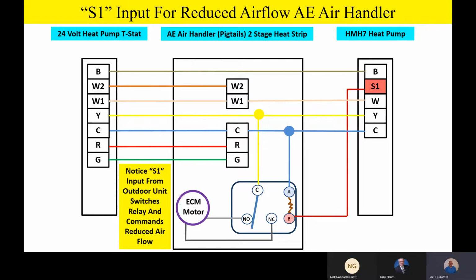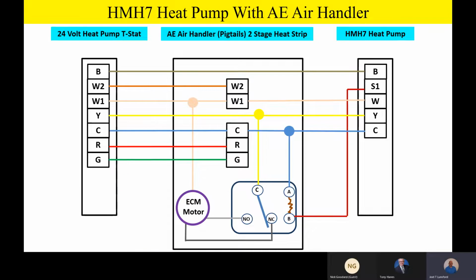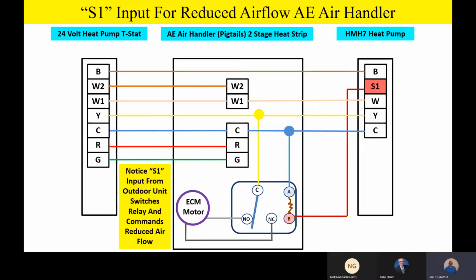Please remember that S1 is our airflow reduction circuit. Let me do that animation again. Look at the relay. When I switch that relay, I'm generating an S1 signal outside, which is actually an airflow reduction signal. So the outdoor unit is making intelligent decisions. When it starts modulating down, around that 60, 65, 50, 55%, whatever point of modulation, it's going to generate an S1 signal to energize that relay and slow the fan down inside to better match the airflow to that reduced capacity.